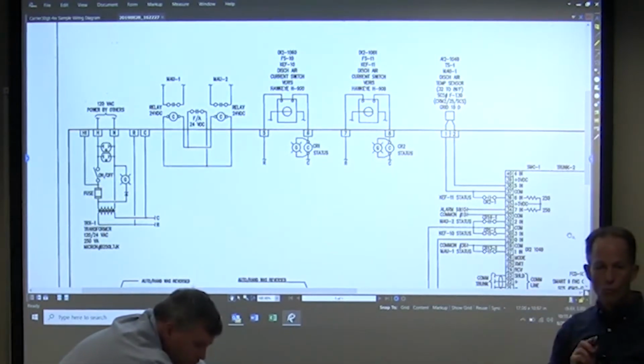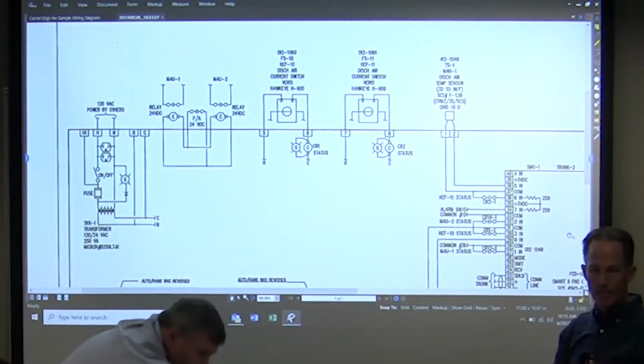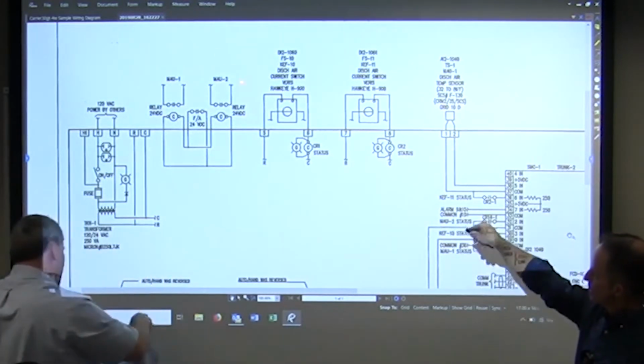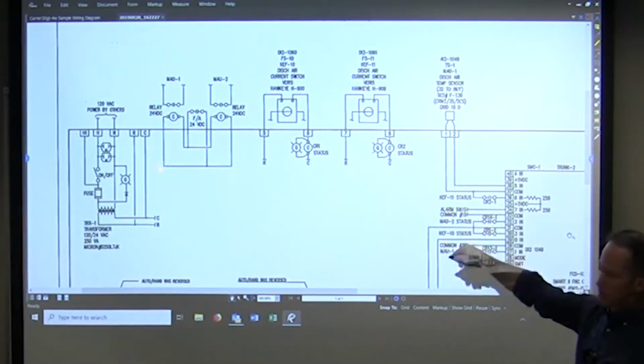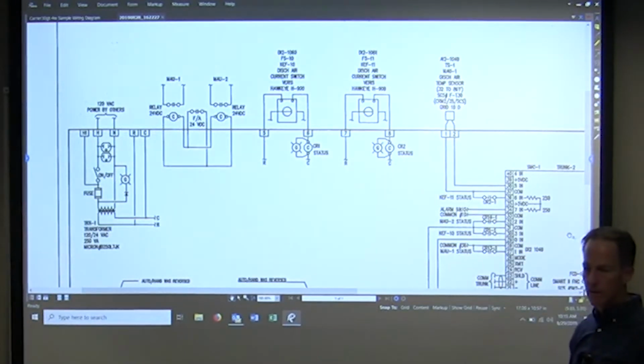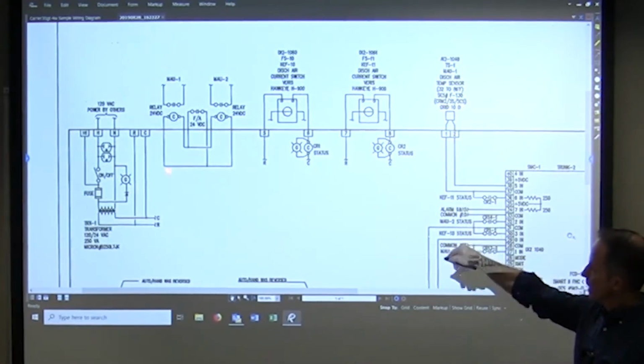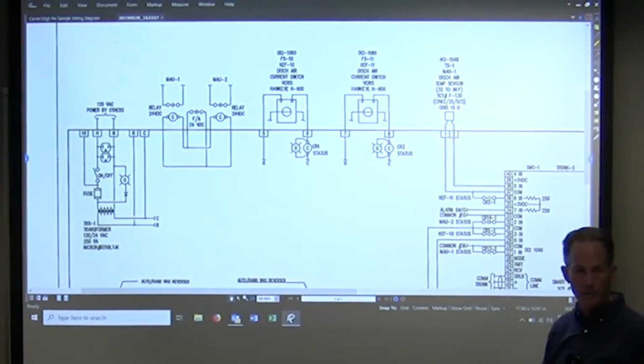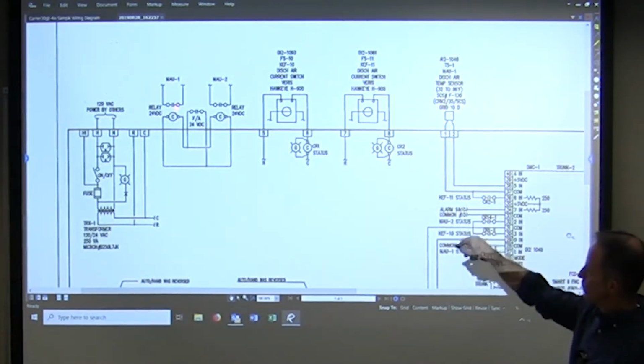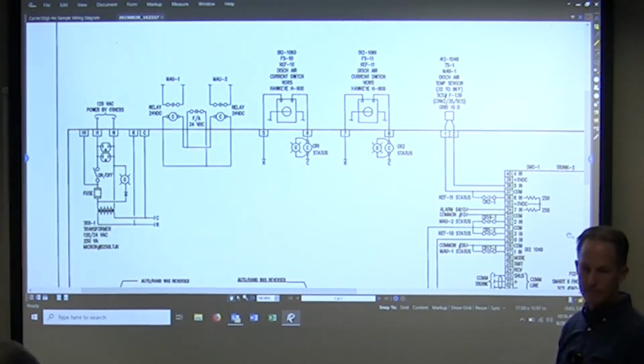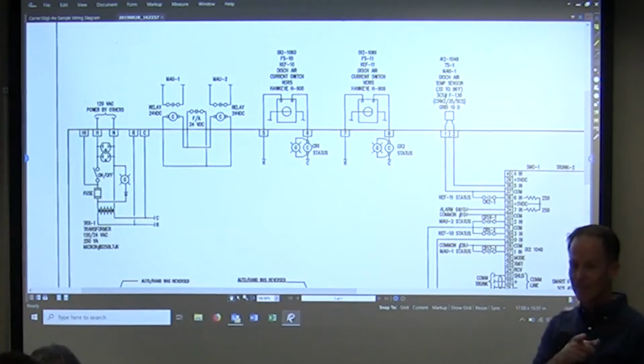So the very first thing that we're going to look at is this little piece right here. We have a couple of things here. F/A stands for fire alarm. Okay, so who can tell me what this is doing? Locking the fan out. Yeah. Okay, so the fire alarm is supposed to basically lock the fan out if there's a fire alarm. All right, will it work? Not the way it's drawn. It's a good drawing, perfect drawing.